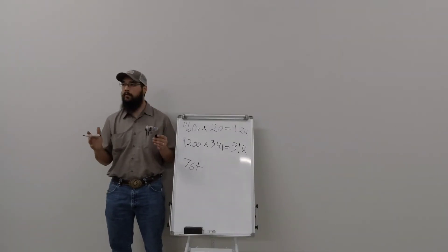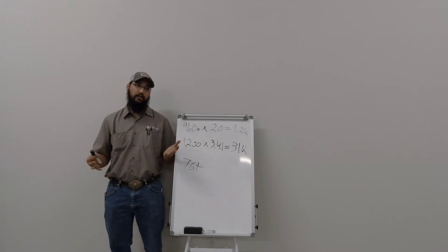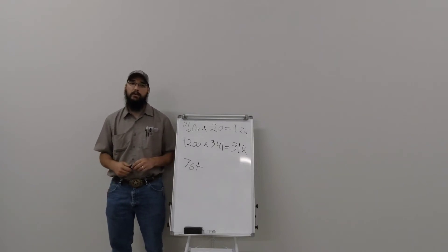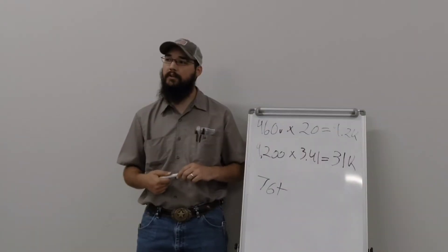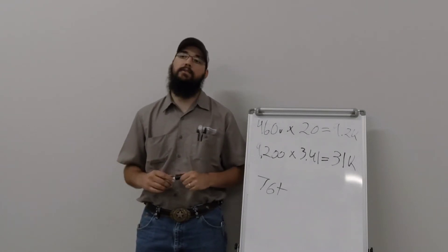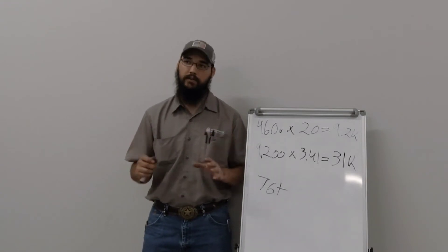That is optimum. Now, if you start looking at ASHRAE standards, according to ASHRAE, they rate a system and its SEER and efficiency and everything at what load condition? An 80 degree return at 50% humidity with a 95 degree outdoor is ASHRAE standards for efficiency of the system.